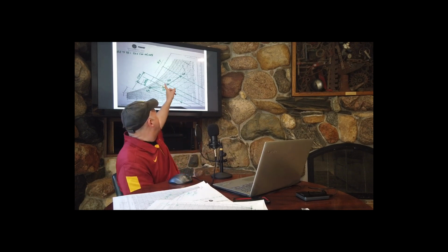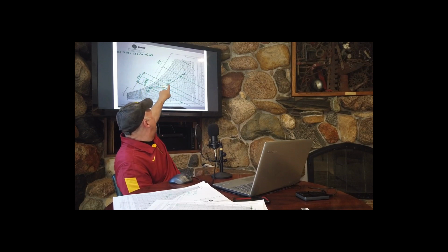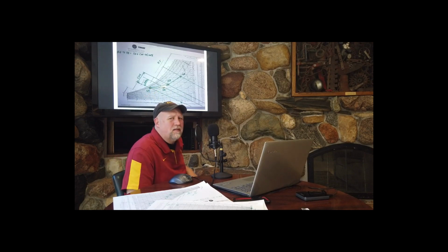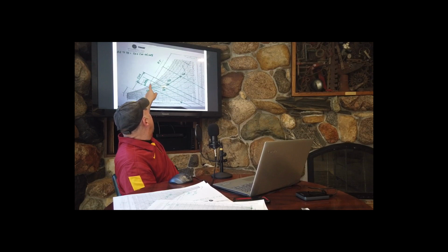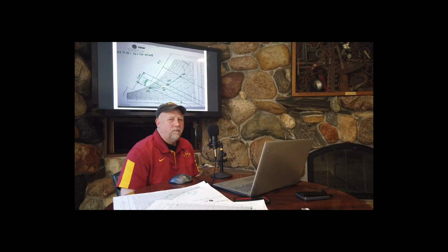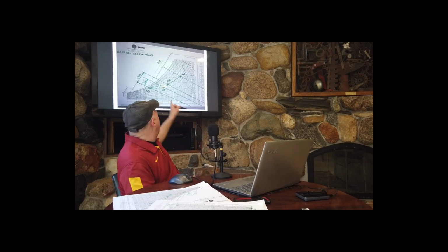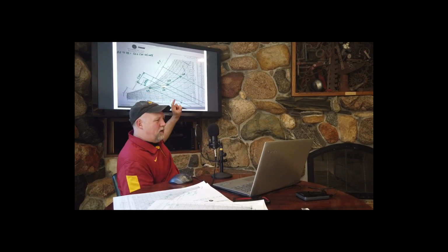Now, once we figure out where this mixed air point is, plot that, and then it goes through the cooling coil. That's this line. It doesn't really look like a straight line like this, to be honest. First, it will go straight over this way, and then once it hits this dehumidification line, it'll drop down. It'll be saturated coming off the cooling coil, and then it'll go across the supply air fan. When it goes across that supply air fan, it'll pick up a few degrees of heat.